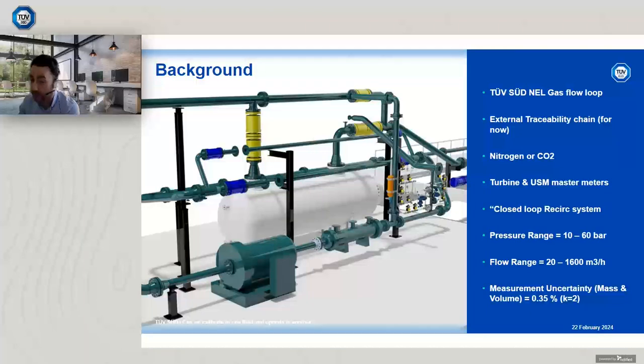So this is one of our newer upgrades, as I say, to CO2, and it's now allowing us to conduct research as to whether a nitrogen calibration can transfer to a CO2 application. And we're looking at evaluating various different meter technologies. So we're going to have differential pressure, so orifice plates, venturi, cone meters, for example, and we're also going to look at ultrasonic, Coriolis, turbine and rotary type devices as well. So a lot of work planned with this facility now that we've upgraded it to CO2. So we're both doing R&D, but it's also commercially available as well for commercial calibrations.